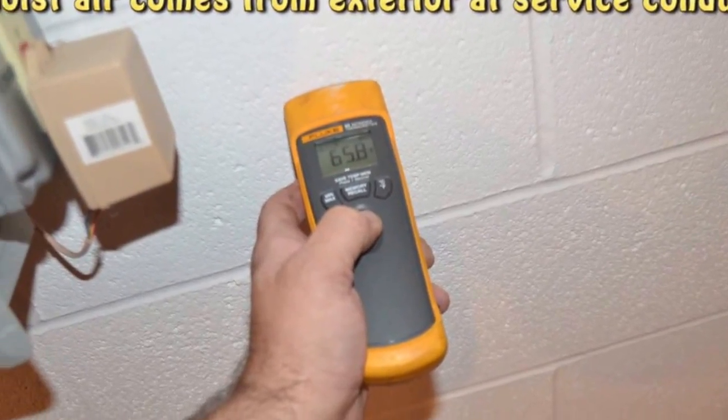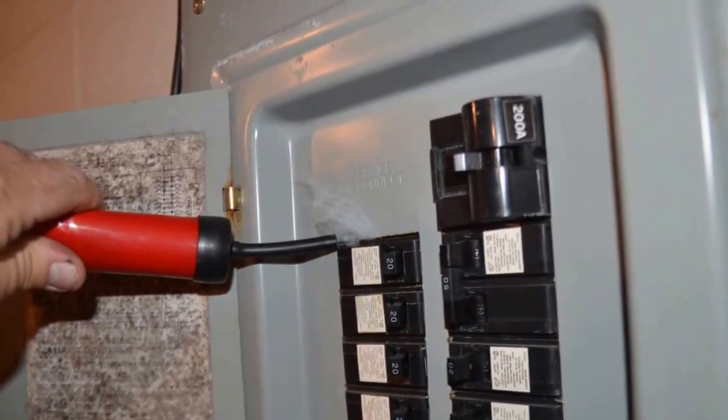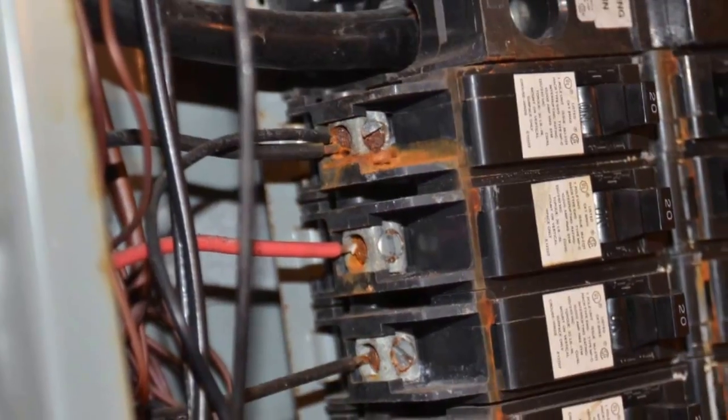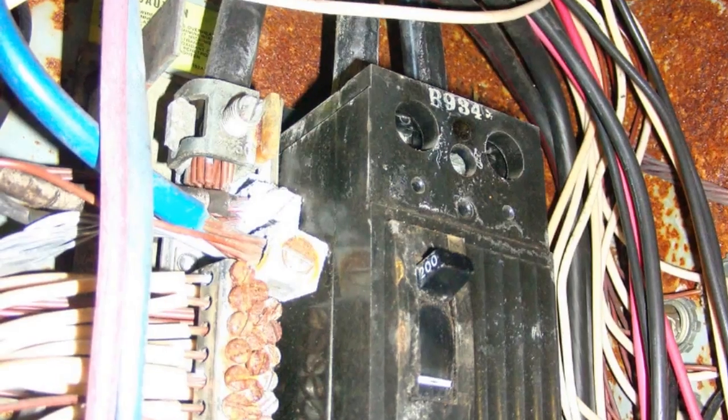Basement foundation walls are colder because they are underground, and the unconditioned, sucked-in moist warm air condenses within the cold electrical panel, causing rust. Rusted panels can cause fires. Many electricians misdiagnose rusted or corroded panels as water leaking in or dripping in.